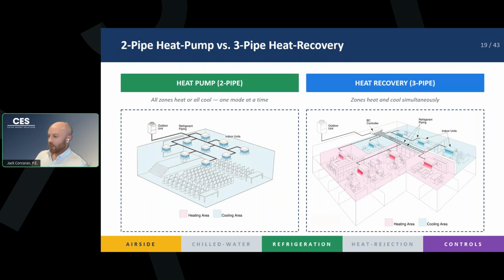Diving into our 2-pipe and our 3-pipe configurations, right? Our heat pump only needs 2 pipes. Essentially, every zone is operating in heating. And if you switch the compressor to cooling mode, or switch our system over to cooling mode, every single zone is going to be operating in cooling, right? So there's no way to get individual zone control in that system. The only way to get individual zone control, right, is with our heat recovery system, and that needs 3 pipes.